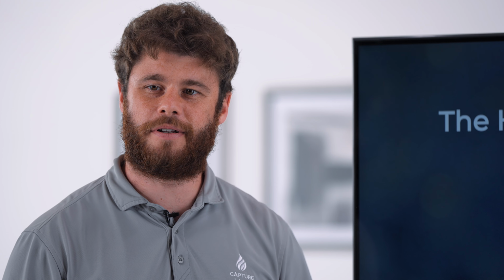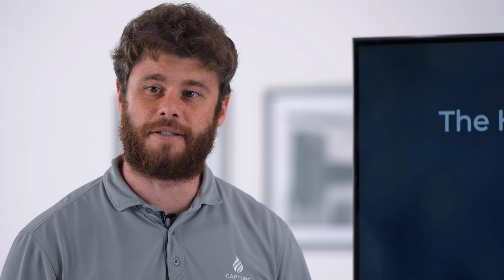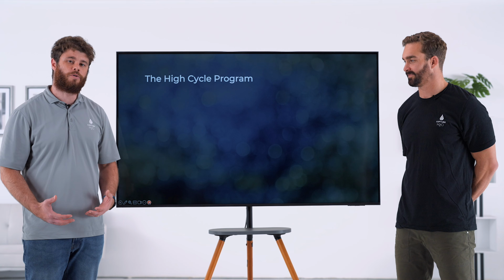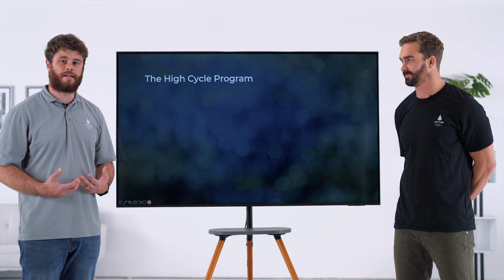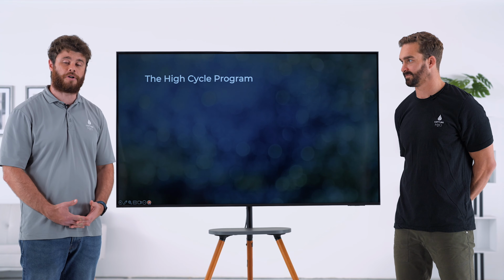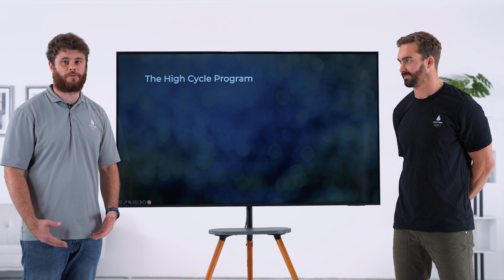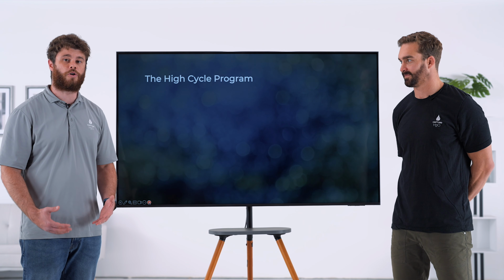My name's Anthony Rowen, lead engineer at Capture H2O, and today I'm going to be introducing you to the high cycle program. The high cycle program utilizes a set of dual alternating high efficiency softeners installed on the makeup line to a cooling tower system to control for scale, corrosion, and bacteria in place of a traditional chemical treatment program.